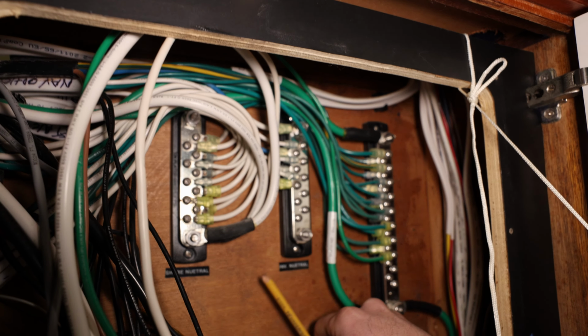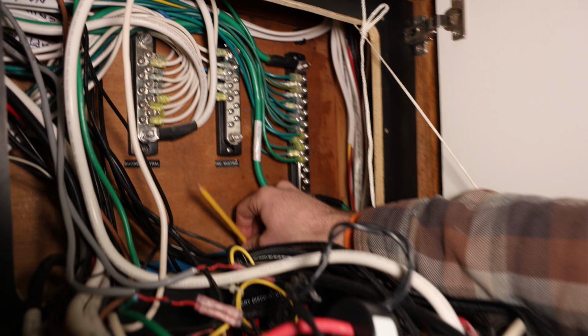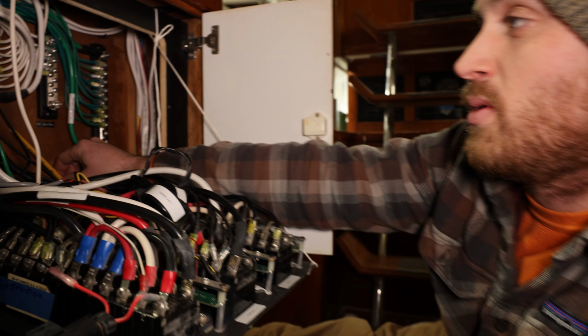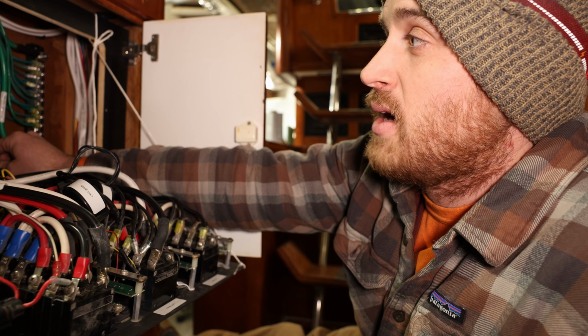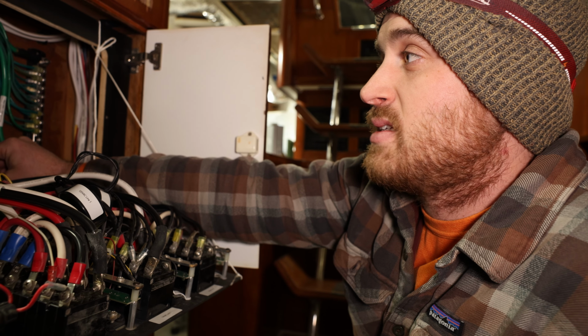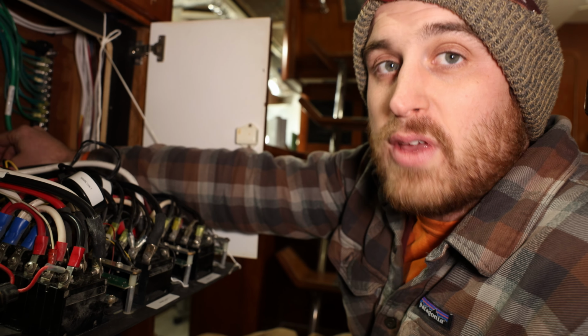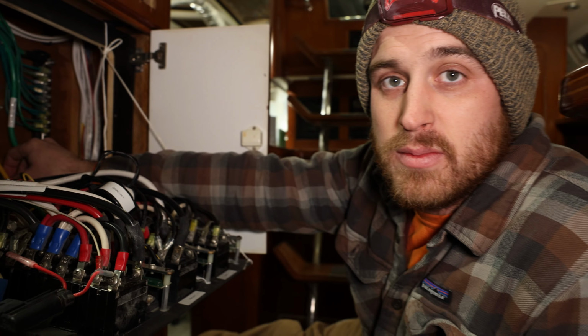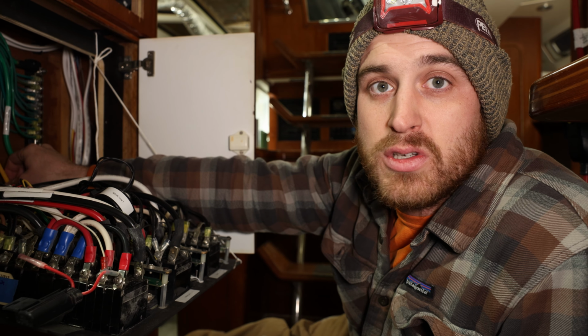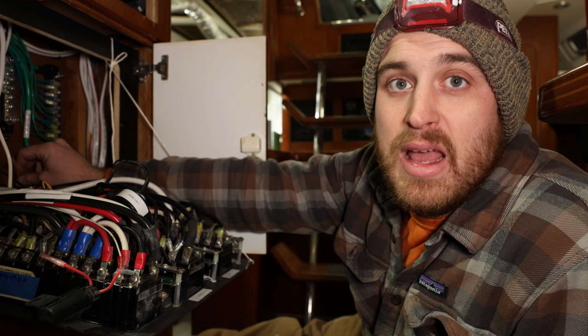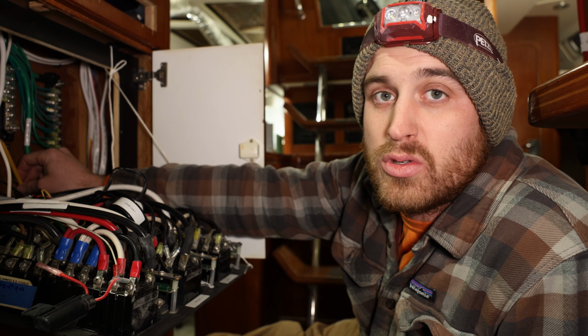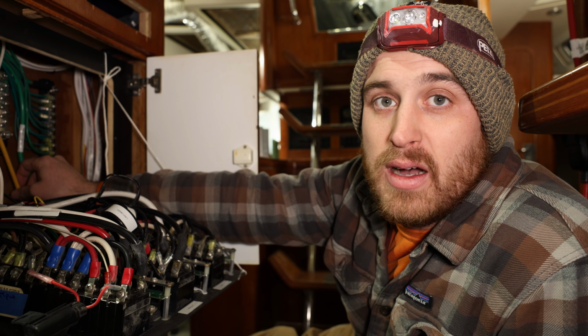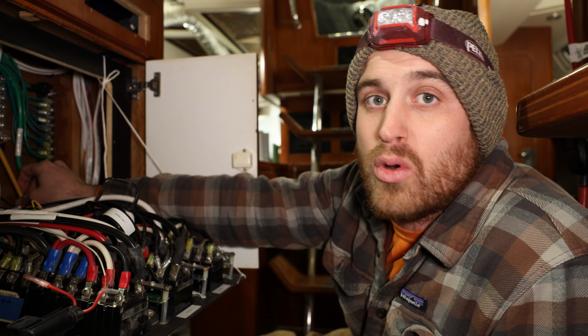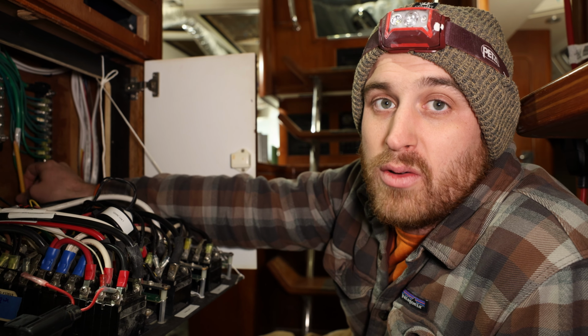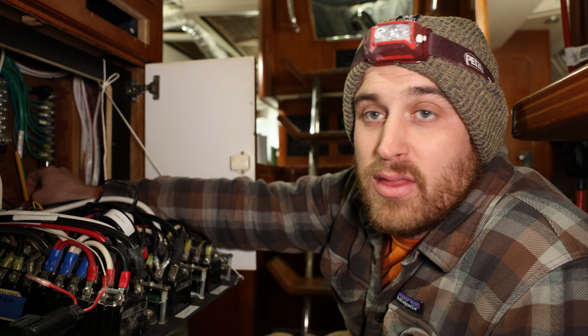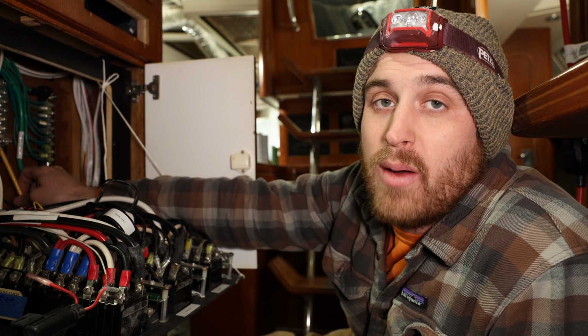This whole design is getting changed with the new Victron Multiplus inverter technology, because inside the Multiplus it's the initial feed for all of our AC power systems. Everything feeds the Multiplus first, and then the Multiplus feeds the panel. It has internal neutral switching, so it identifies whether the neutral-ground bond between the white and green wire only happens at the source of power, and only one source of power at a time.